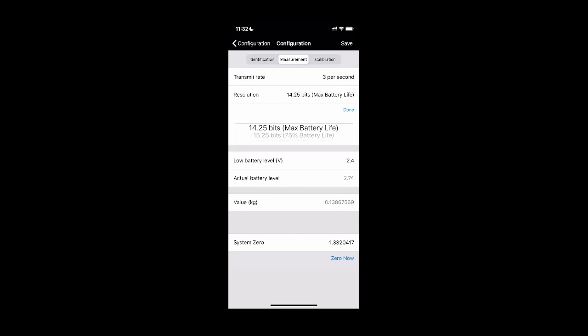This is an important spot for the 0 now, as we can see in blue. If we were bringing our load cell, let's say between cold temperatures, warm temperatures, like in a wintertime environment to indoors, outdoors, once it stabilizes temperature, you might have to double check. Potentially, you might have to re-zero a load cell if it drifts based off temperature, if you're sitting in a cold environment. So that's a normal item. And so this might be where you would have to actually reset that 0 in here. This pretty much covers all the measurement page.